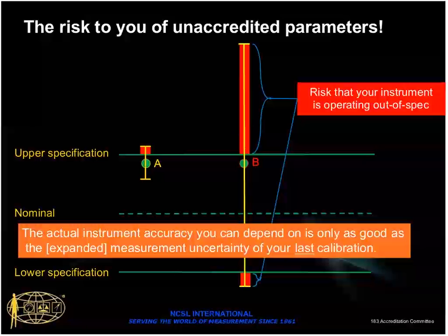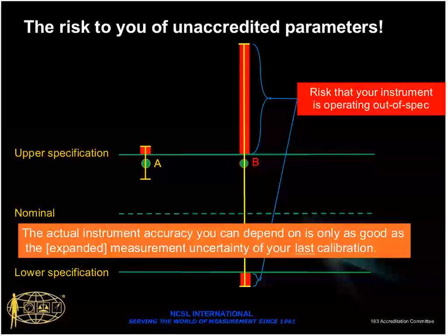And what I'm telling you is that in my practical experience, oftentimes when I'm asked as a technical consultant to look at the differences between calibration measurements between two different laboratories, I find that sometimes they don't actually even include a measurement in the report, so I don't know if they made the measurement or not. But when I look at the trace information, I can at least see which instrument they used. And having been a long-term employee of HP, I know those instrument block diagrams well enough.